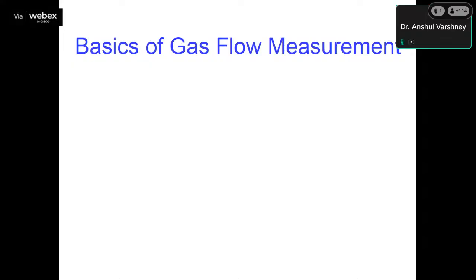Basically, for water flow calibration, we have a primary method where we provide calibration with the help of a gravimetric system or weighing system. In the case of gas flow, we have a secondary standard. Basically, this works on the comparison method. However, we are in the process of developing a primary standard for gas flow.